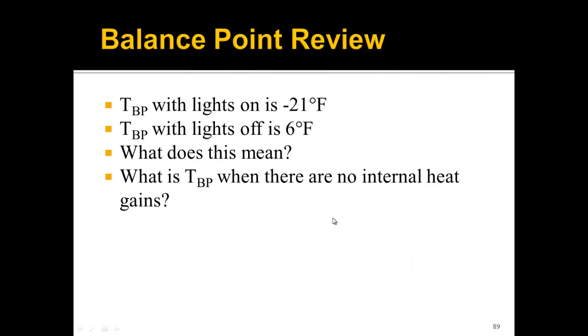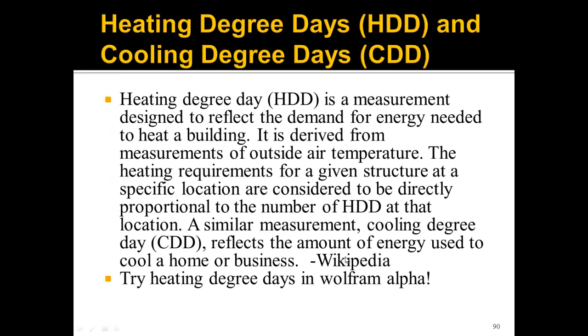Now let's talk about heating degree days and cooling degree days, and we'll come back to why balance point matters here. A heating degree day is a measurement designed to reflect the demand for energy needed to heat a building — the higher the heating degree days, the more energy you need for heating. Similarly, cooling degree days reflect the amount of energy used to cool a building; the higher the cooling degree days, the more cooling energy is required.